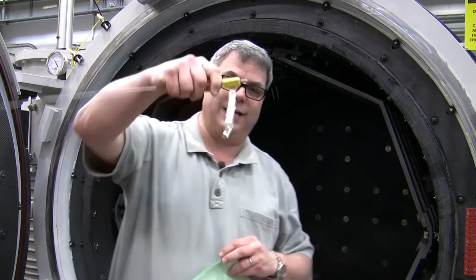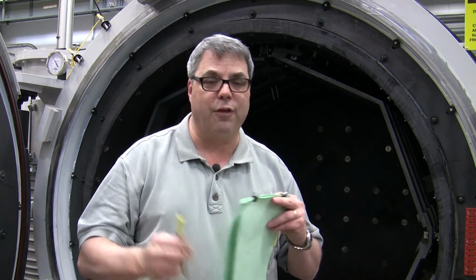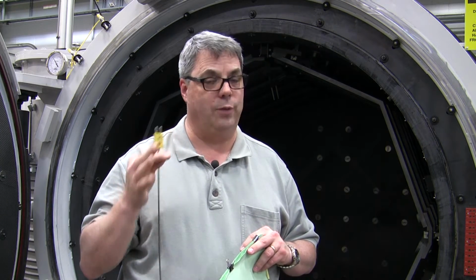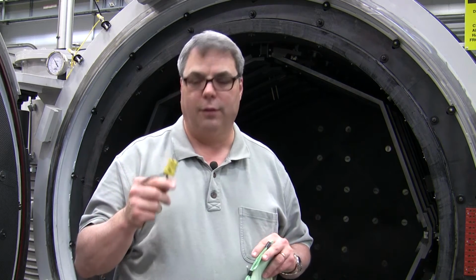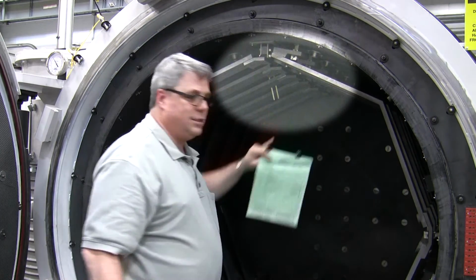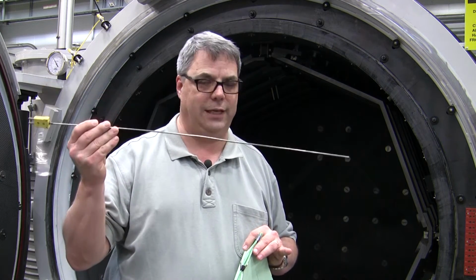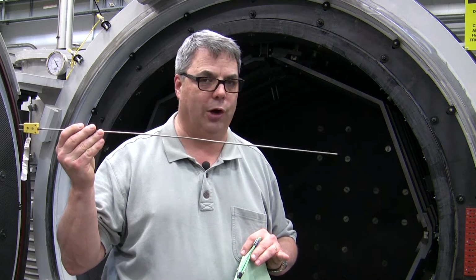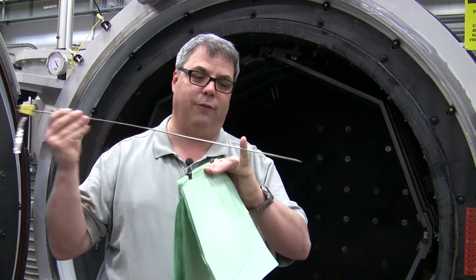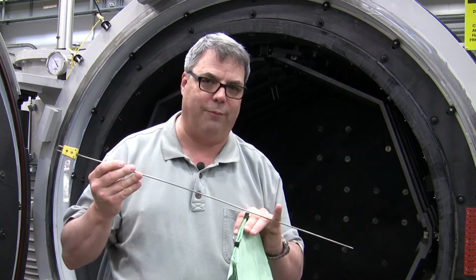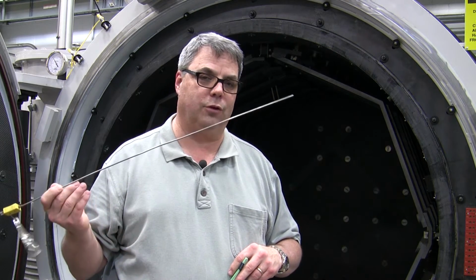So if a thermocouple is damaged, broken, and needs to be replaced, the thermocouples have tags on them, which are attached to the certification sheet. If the thermocouple is from the same family or extremely close within the specification of 1.2 degrees, roughly, then as long as your book has recorded the as discovered and as found thermocouple immersion depths, if I break a TC, I can prove to the auditor that I'm replacing it with a like TC with equal to or exactly the same calibration curve, and I've recorded where it was, so when I put my new TC in for my insertion depth, I'm guaranteeing it's exactly where it belongs and where it came from. In that case, most inspectors now are saying you do not have to recertify the equipment because you've recorded as found, as discovered, as tested, as left information. So there is not the need to recertify the furnace upon controlled thermocouple replacement.